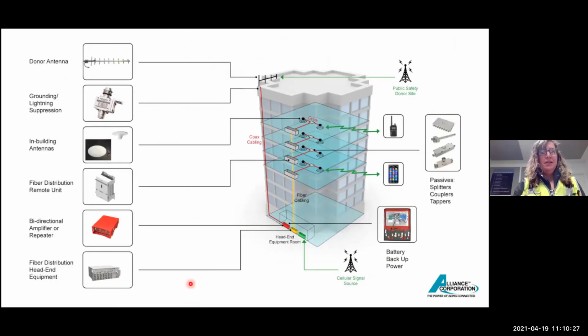It may have a fiber system instead of coax, so we might have fiber coming in together. Similarly, your receiver just looks like a big box, and the head end equipment also looks like another box. You may need to enclose the cabling in a 2-hour rated enclosure, so you need to make sure you have room and are coordinating where that's going to go.